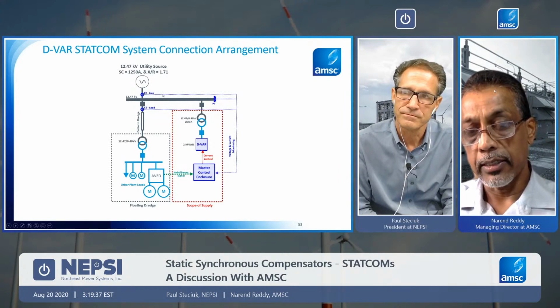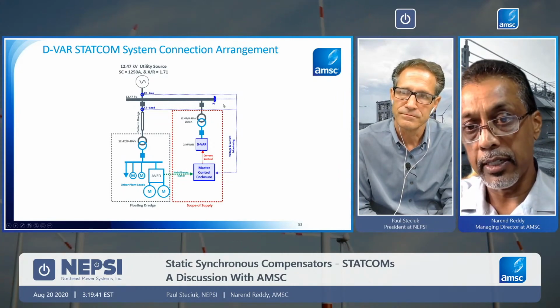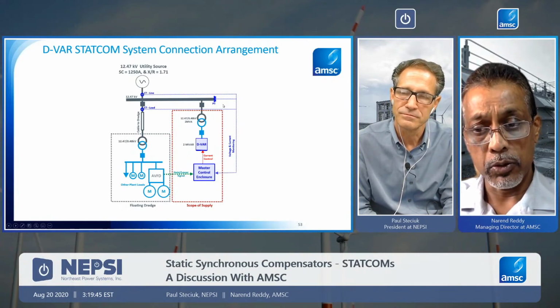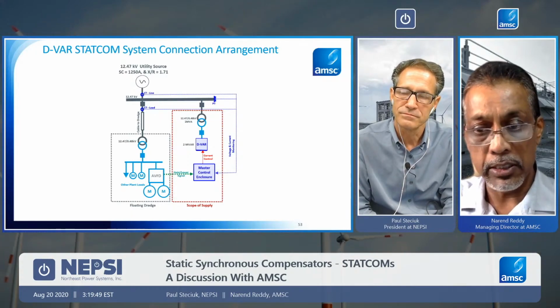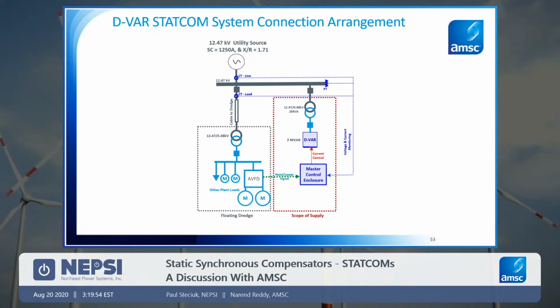Now, in this case, we monitor the supply side currents. We look at the load side currents. We look at the 12.47 kV voltage, because we want to make sure we are addressing flicker or voltage, depending on what control mode is utilized. All of this signal is fed into the master controller. We also get a signal from the hoist operation telling us when they're operating. That helps us fine-tune the problem and make the system more effective as and when the hoists are operating. The master controller then controls how the D-VAR system injects current: how fast, how frequently, and at what current level. All of that is dictated by the algorithms in the master controller.